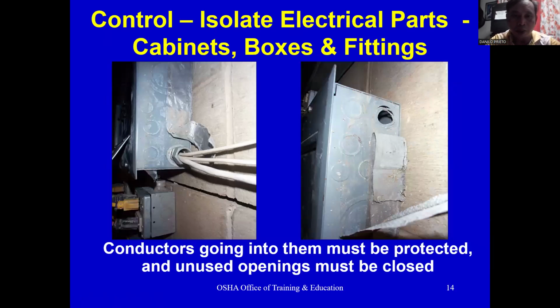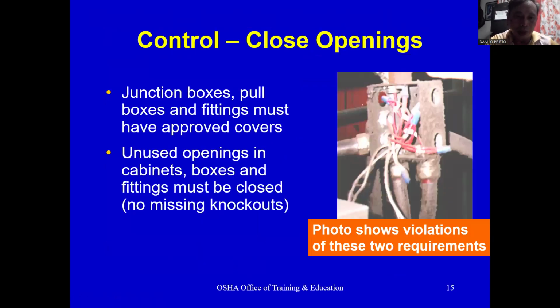Next, control: isolate electrical parts, cabinets, boxes, and fittings. We have here the example pictures. Conductors going into them must be protected, and unused openings must be closed. Control: close openings. Junction boxes, pull boxes, and fittings must have approved covers. Unused openings in cabinets, boxes, and fittings must be closed, with no missing knockouts. The photo shows violations of these two requirements.